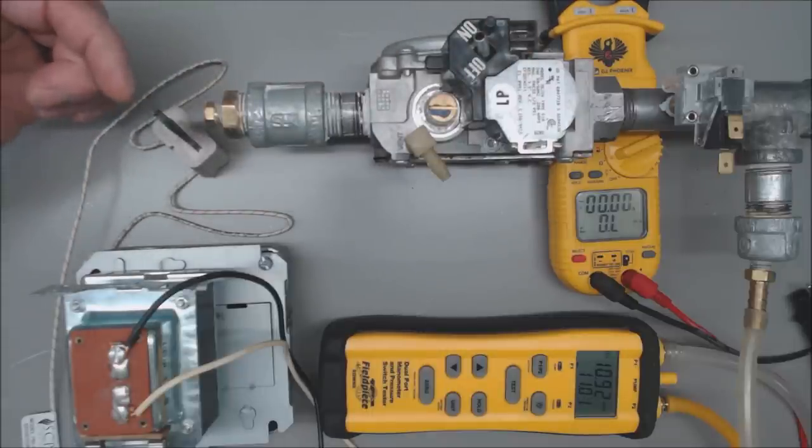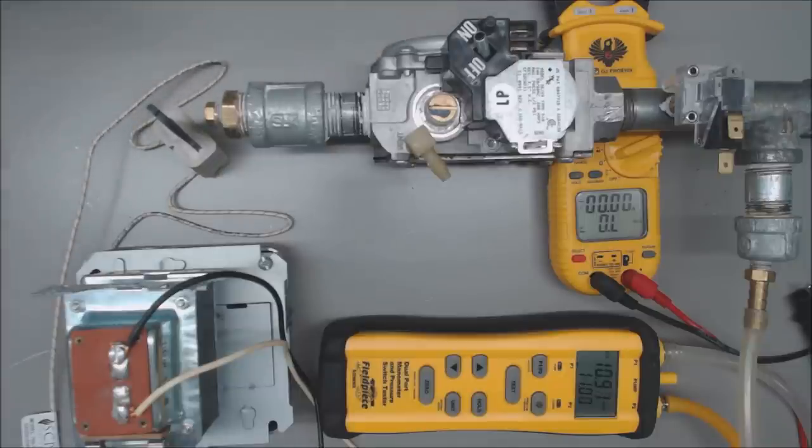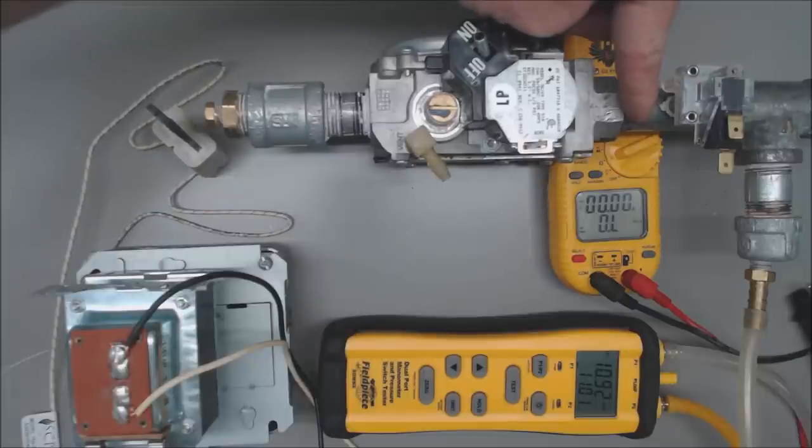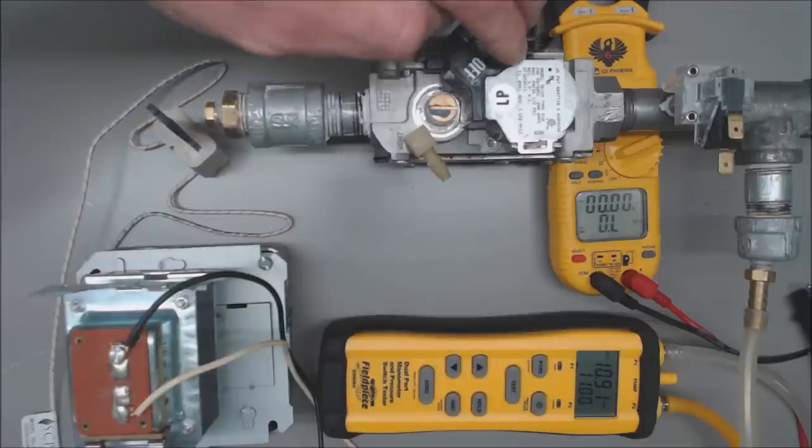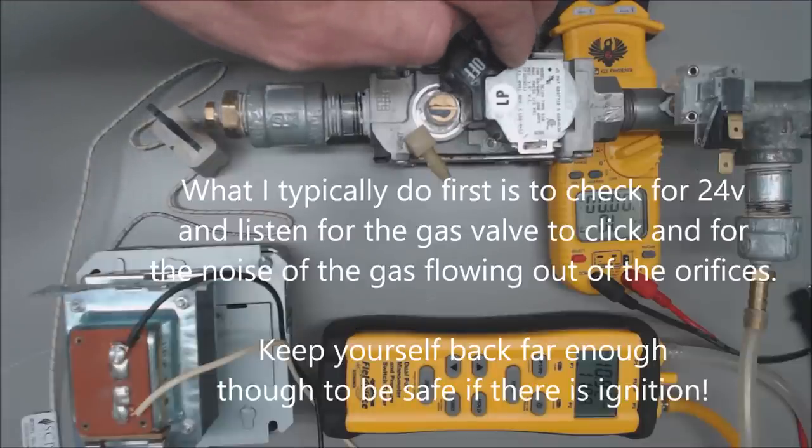So if you do have a hot surface igniter turning cherry red but you do not have gas flow, then what you need to do is check your inlet gas pressure first. As well, you're going to check your outlet gas pressure and verify that you have 24 volts heading into the electrical gas valve.